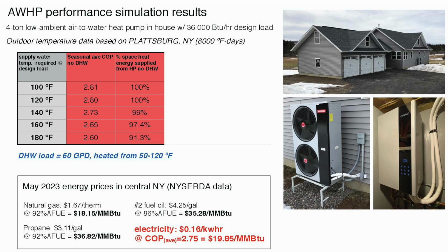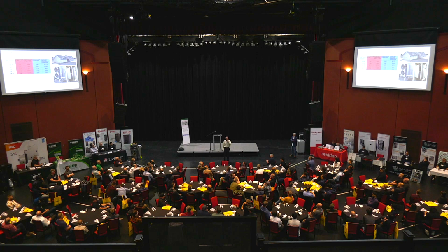And you're still going to get, over here we're showing percentages of the seasonal space heating energy that's being supplied by the heat pump. And even if your system needed 180-degree water at design with outdoor reset, we can do about 90% of that load. Now that's a 4-ton rated heat pump, like the units that are here, nominal 4-ton, in a house that at design load is 36,000 BTUs per hour.